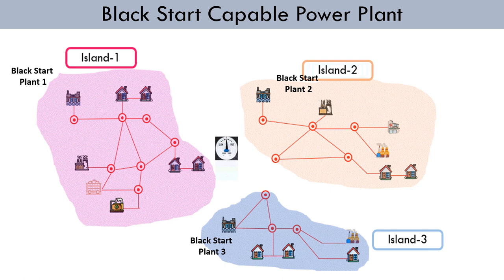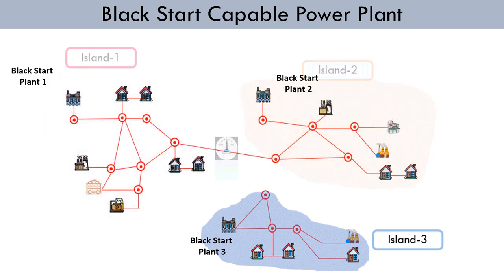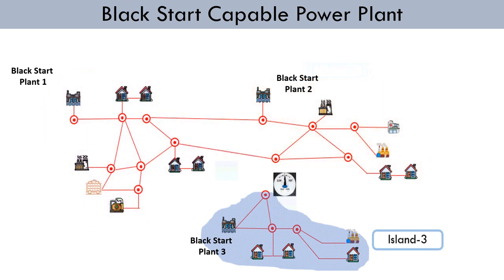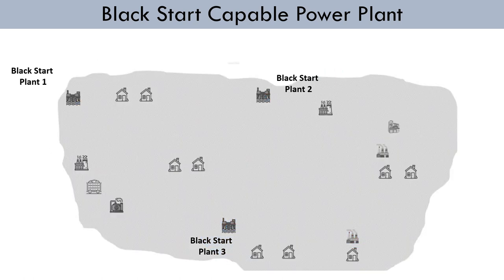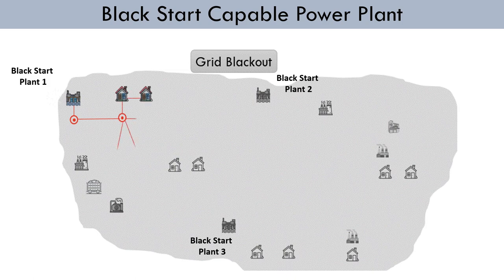Multiple islands also help in quicker restoration. These islands are then synchronized at predefined locations through a synchroscope or synchro check relay. With this, a large unit is formed, which is more stable and robust and able to have better voltage and frequency control.